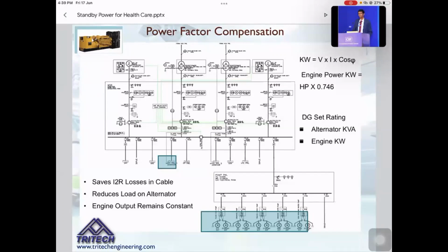When you compensate the large loads not connected to the APFCR, like your large chillers and pumps, it will reduce the I2R losses. It drastically reduces the energy losses in the cables. In our projects, we put smaller fixed capacitors as compensation for all the large loads at the end of the system. The automatic power factor controller feeds the remaining; maybe up to 50% is covered by the manual fixed capacitors, and 50% will be automatic. It also reduces your investment on the automatic power factor system, which needs to cater only to the fluctuation. So it saves the I2R loss and reduces the load on the alternator.